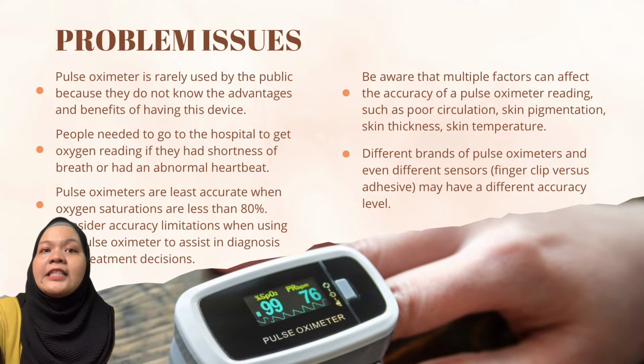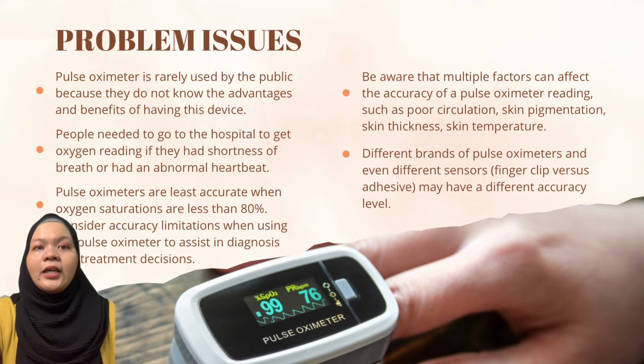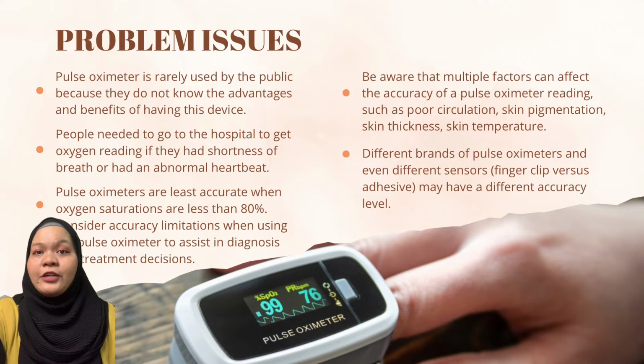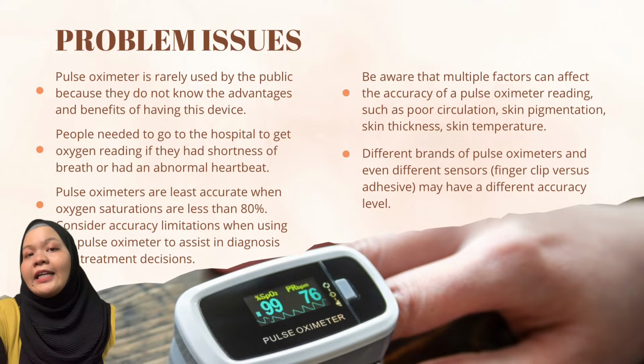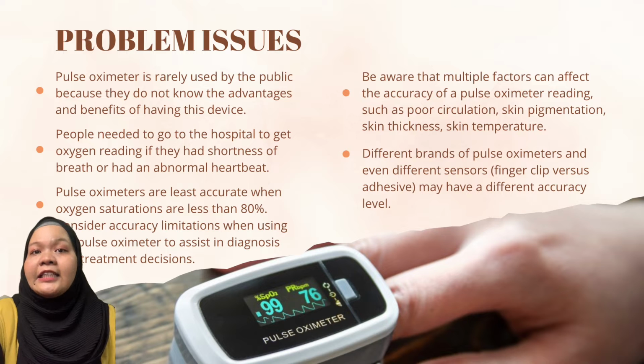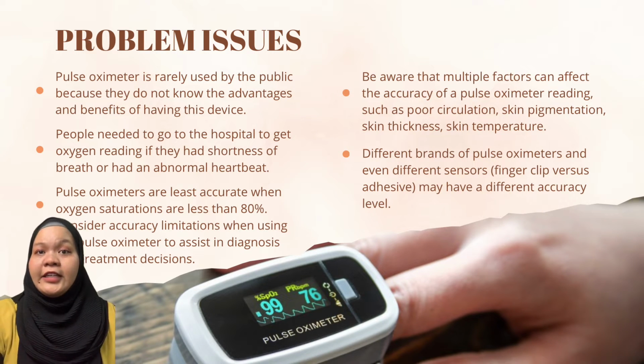Consider accuracy limitations when using the pulse oximeter to assist in diagnosis and treatment decisions. Use the pulse oximeter reading as an estimate of blood oxygen saturation. For example, a pulse oximeter saturation of 90% may represent an arterial blood saturation of 86 to 94%. When possible, make diagnosis and treatment decisions based on the trend in pulse oximeter readings over time rather than absolute thresholds.